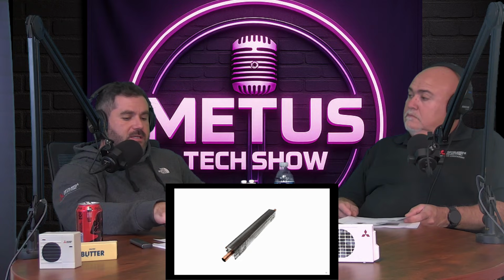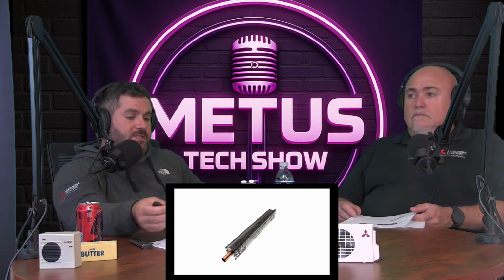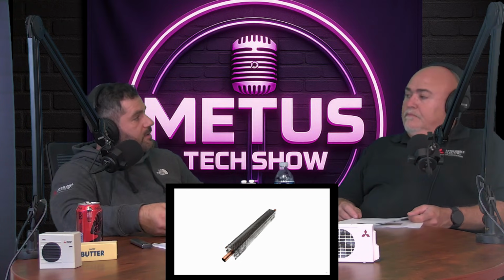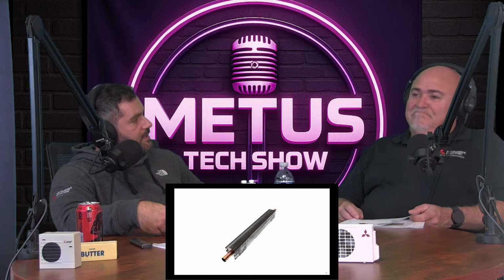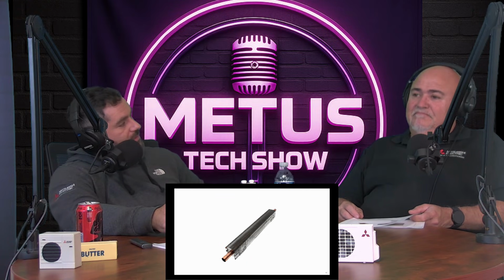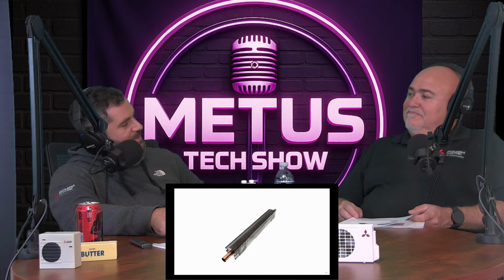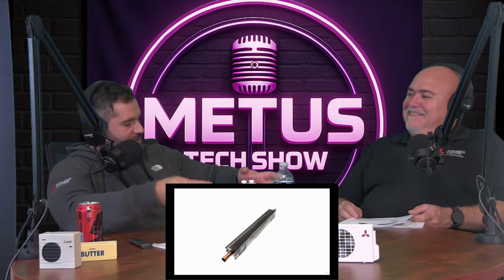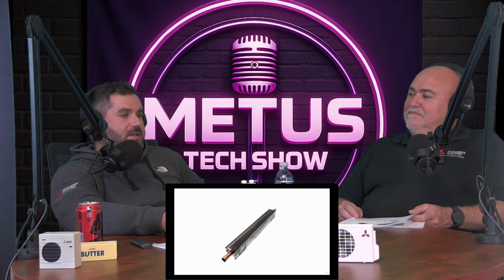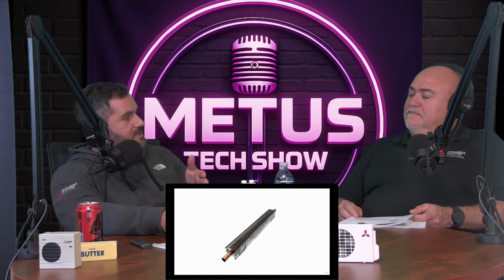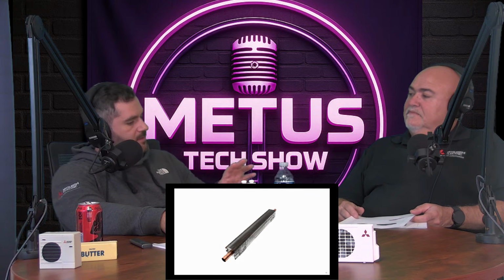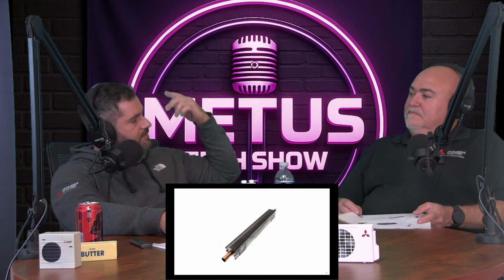So first is just baseboard. So this looks like little trim board on the bottom of your wall, and typically it's metal, and if you ever knock it down, it's a pain in the butt to get back on there, especially those end caps, making sure they line up perfectly. But it's just fin tube, right? It's one tube and then a bunch of aluminum fins that help move that heat off of the pipe, and then typically there's a little metal decorative cover over it.